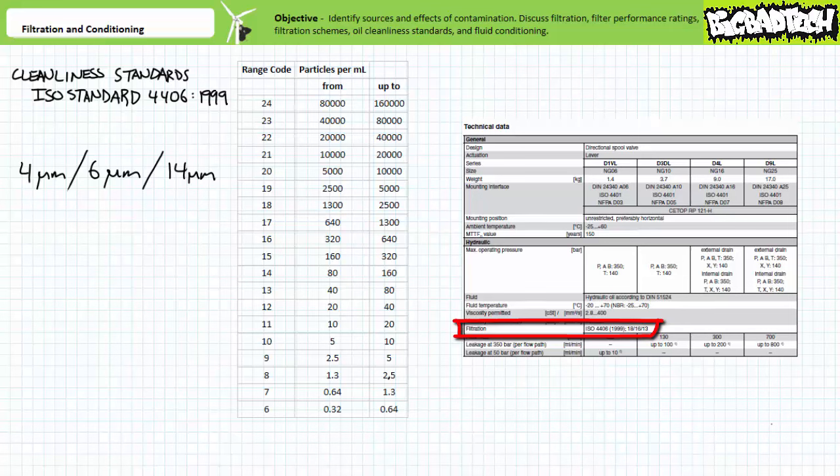For example, this directional control valve data sheet is expressly calling for oil with an 18-16-13 cleanliness rating. This means anywhere from 1,300 up to 2,500 particles greater than 4 microns, but less than 6 microns are present per milliliter. Anywhere from 320 up to 640 particles greater than 6 microns, but less than 14 microns are present per milliliter. And anywhere from 40 up to 80 particles greater than or equal to 14 microns are present per milliliter. If the data sheet says a particular component necessitates an oil with a two number ISO cleanliness code, it ordinarily means ignore particles less than or equal to 4 microns and concentrate on the 6 and 14 micron bin. For example, if this directional control valve didn't care about particles less than or equal to 4 microns, it'd be calling for 16-13 oil.